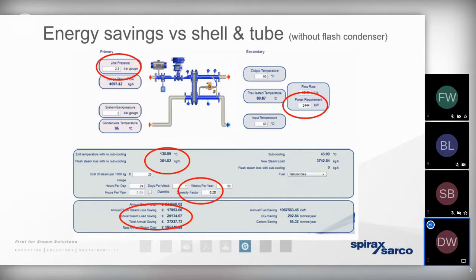It also means that we've got significantly more heat per kilogram than water. And that means that we need to add all of that latent heat energy to it to make water boil, to change state to steam. And then we've got the high speed of heat transfer, which is steam's got a rate of heat transfer that's approximately 3 times greater than water. So all of these factors mean that we can get away with condensing steam at a much, much lower temperature and therefore at a much lower pressure. And because the steam tables tell us that there's more useful energy in steam at a useful pressure, it means that we're going to enjoy significant cost-saving benefits by moving towards that instantaneous solution.